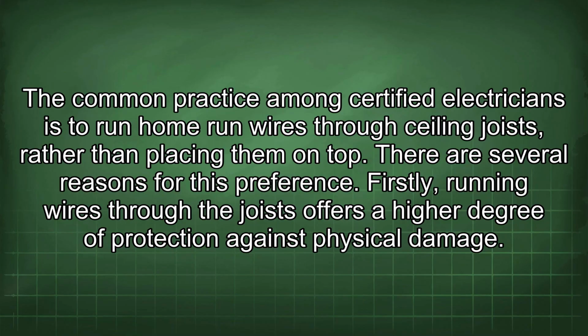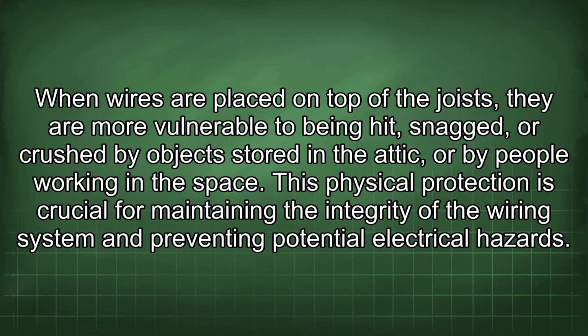A common practice among certified electricians is to run home-run wires through ceiling joists rather than placing them on top. There are several reasons for this preference. Firstly, running wires through the joist offers a high degree of protection against physical damage. When wires are placed on top of the joists, they are more vulnerable to being hit, snagged, or crushed by objects stored in the attic or by people working in the space. This physical protection is crucial for maintaining the integrity of the wiring system and preventing potential electrical hazards.